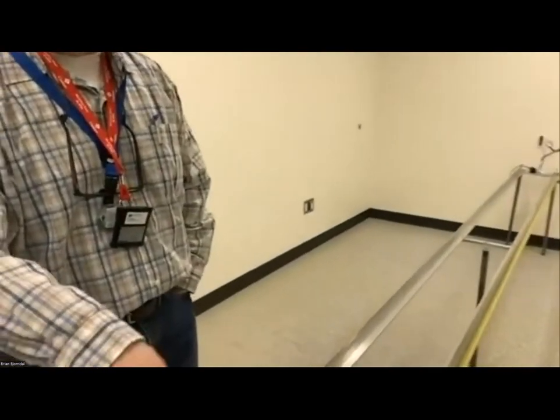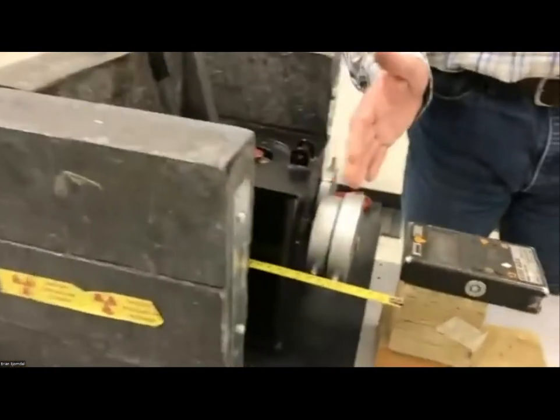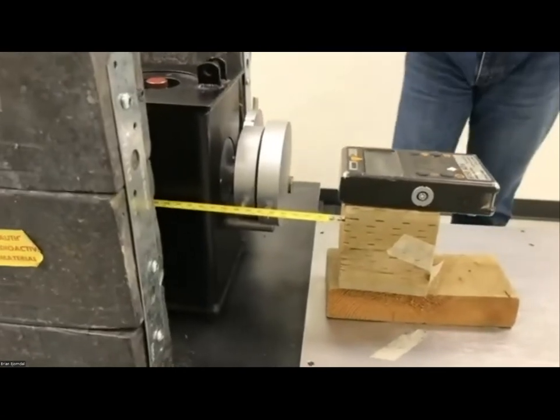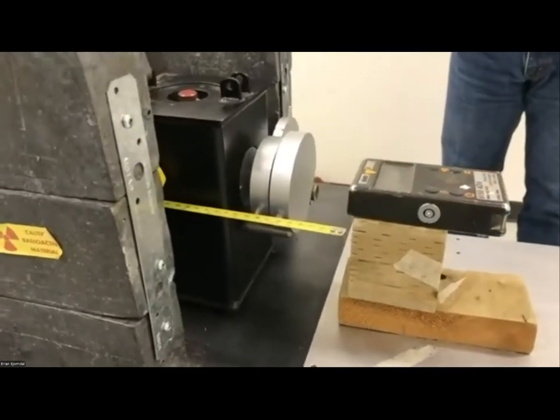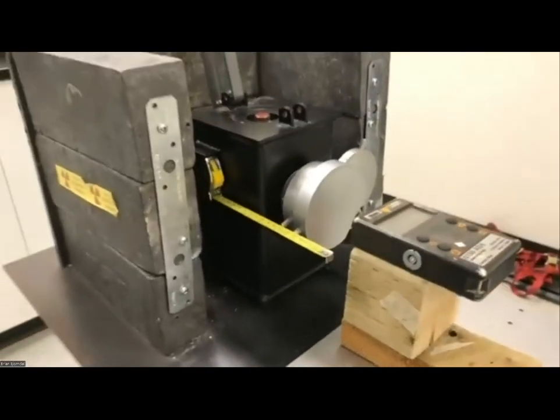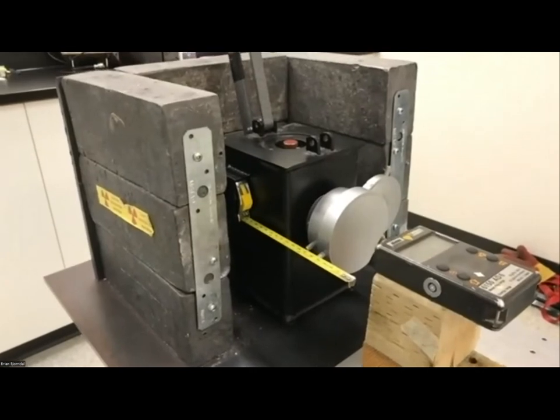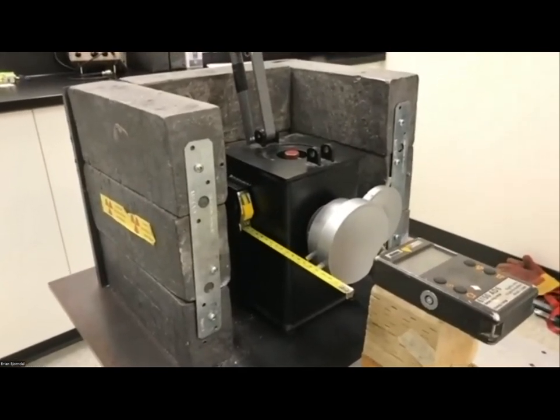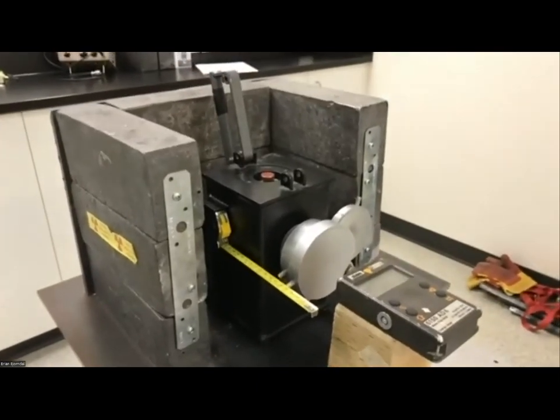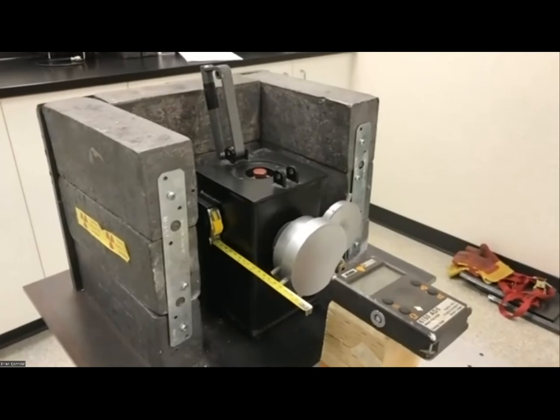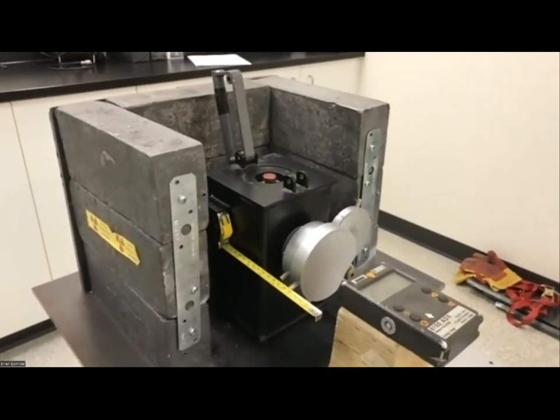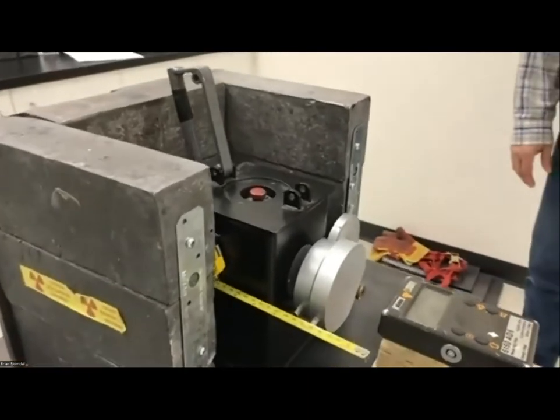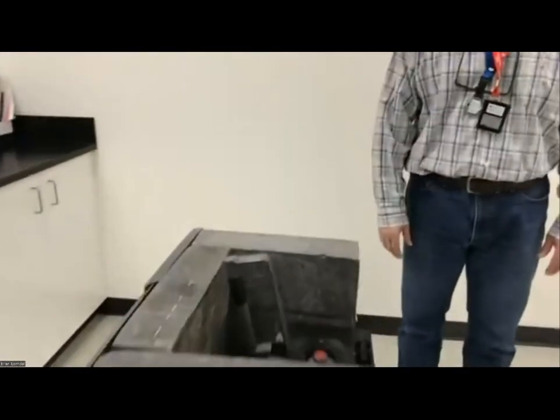Okay. Richard's asking, how do you ensure the survey meter is set up centrally in the beam axis? You mentioned the wood shims, but you might. Yeah. So we've got schematics on the cesium source, and we know the center of the height, so we actually measure up from the table and then away from the source, so we can get within the beam. And the beam spreads out quite nicely. With the manual for the source and our documentation, there's a table on what that beam size and dimensions are, based on your distance from the source. So really, we use just physical measurements to get it at the right distance from the source and at the right height. And we confirm that before we do the measurements. And again, if we do see anomalies with the measurement, that's the first thing we're going to check, to make sure it's sitting in the right zone.